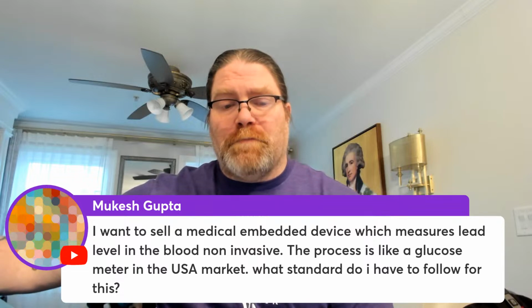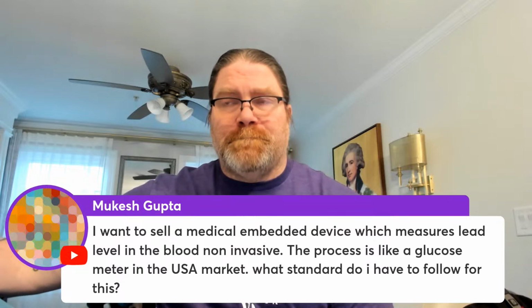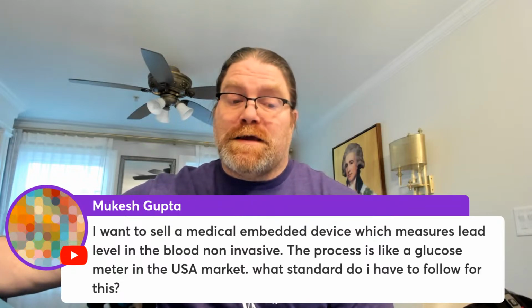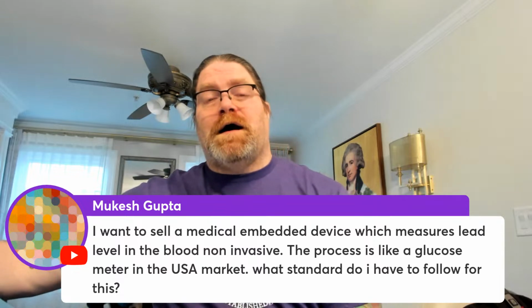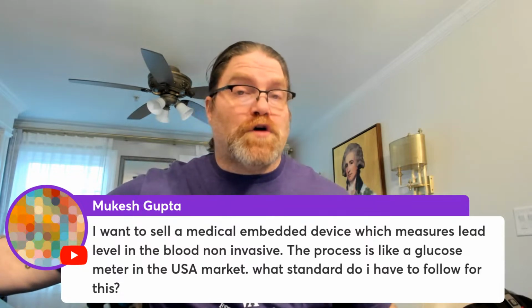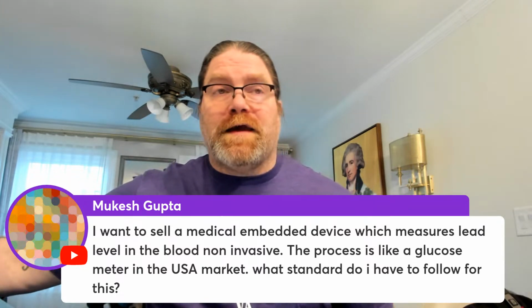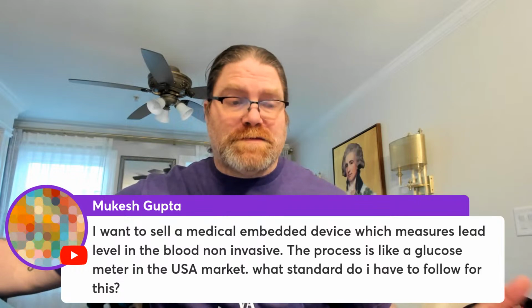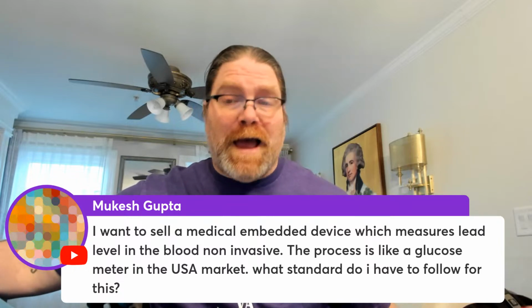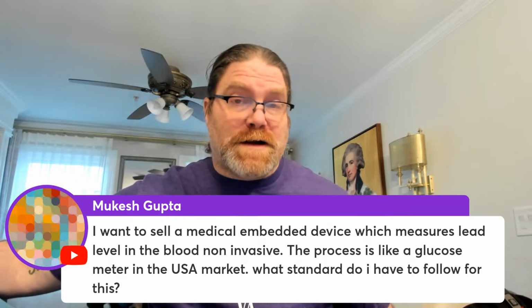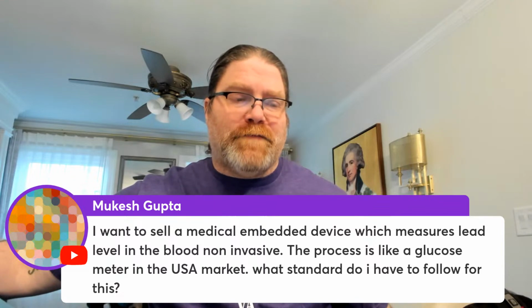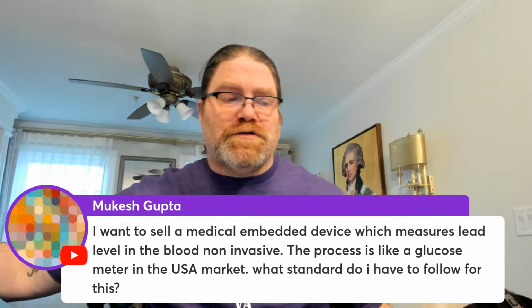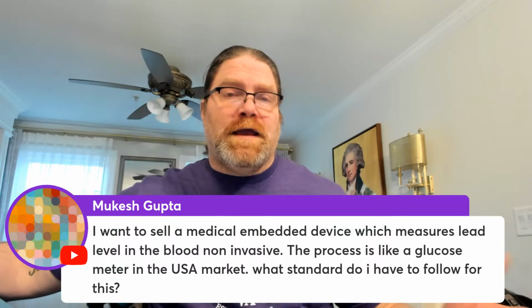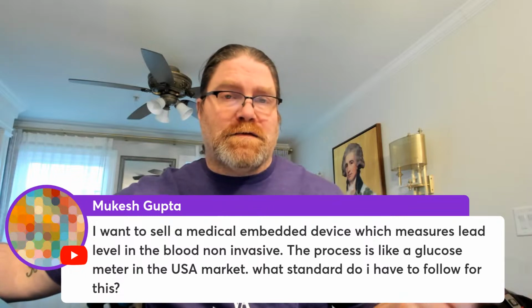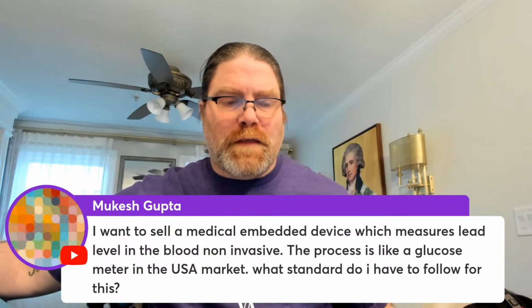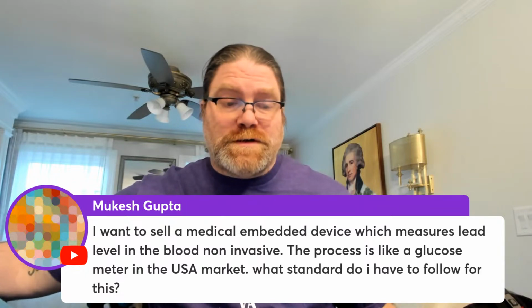You collect the drop of blood, and then you measure that. If it's going to be an OTC product, then you'd want to have something that has auto calibration. If you have a prescription-only device, then it could be calibrated by the user, maybe the doctor, and you'd normally have a sample specimen that would have a known quantity of lead in it, and you calibrate it against that and then test your blood. So that would definitely be a way.